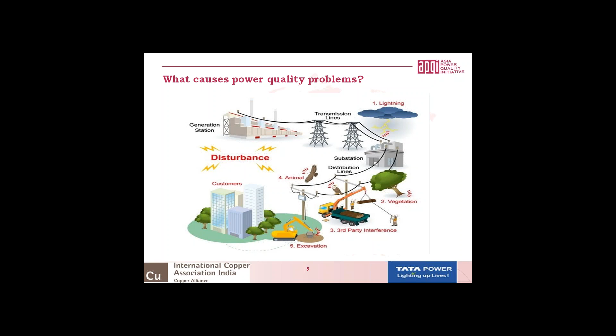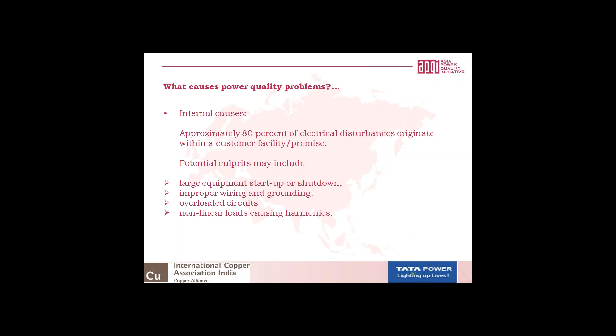Now, what causes power quality problems? Our experience shows that approximately 80% of the electrical disturbances originate within the customer facility or premise. The potential culprits may include large equipment startup or shutdown, improper wiring and grounding, overloaded circuits, and non-linear loads which cause harmonics. Most of these problems originate within the premise of the consumer, but due to lack of awareness, many consumers are not even aware that the problems they are experiencing are actually generated within their own premise and are in their control.